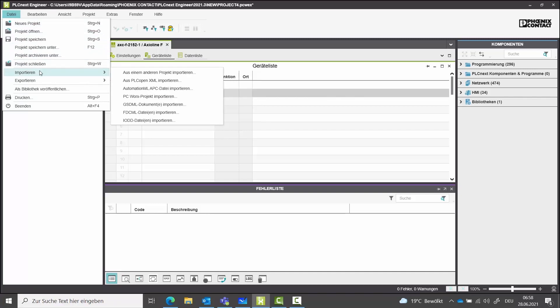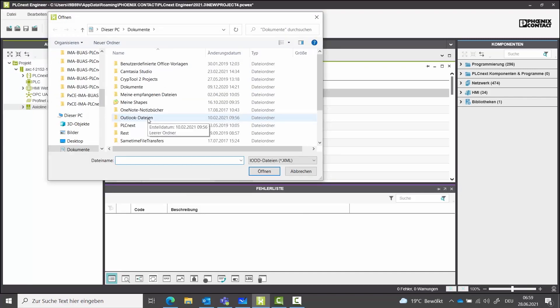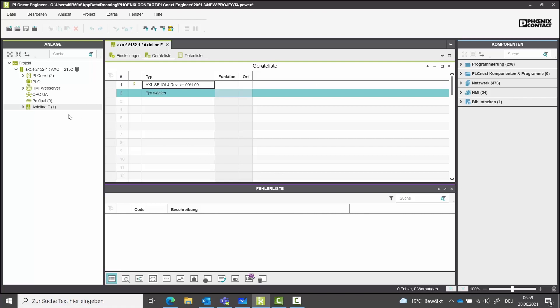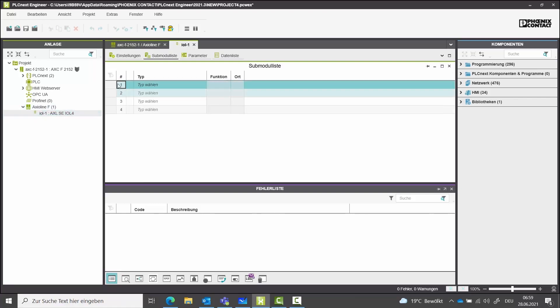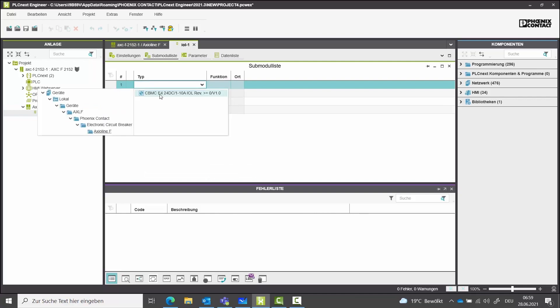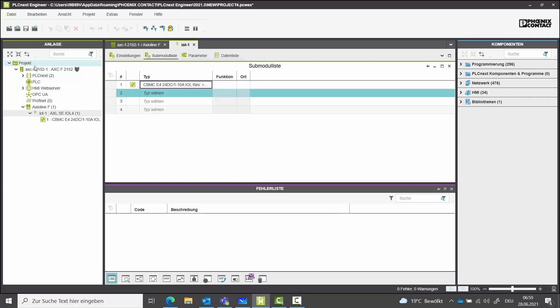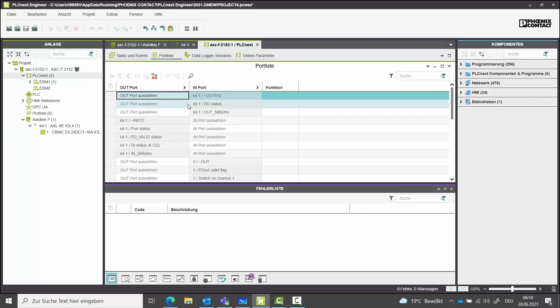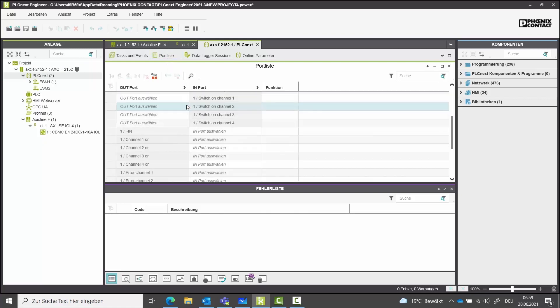The new application is programmed in the software. For this, we import the device description of the IO-Link device — the so-called IODD — for example for the CBMC device circuit breaker. The parameters of the CBMC can then be used directly in the application programming and adapted as required by the new application.